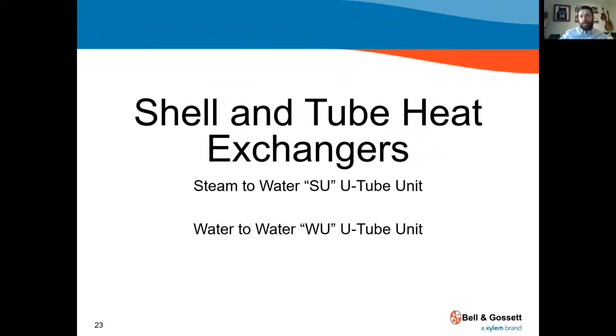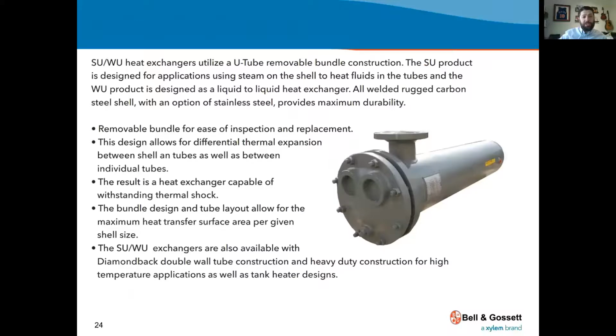They look the same. Basically, you're bringing water into the shell and into the tubes. The steam unit's got steam in the shell, water through the tubes. Most of the time, I should say, not all of the time. So here's a look at that U-tube unit. You've got the shell, and the shell's bringing the steam into that top flange that you can see at the top of it, and then condensate comes out of the bottom. Generally, we can change the configuration if you don't want the flange exactly there. There are a few options available.